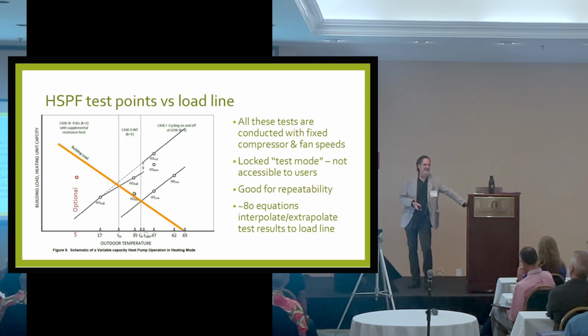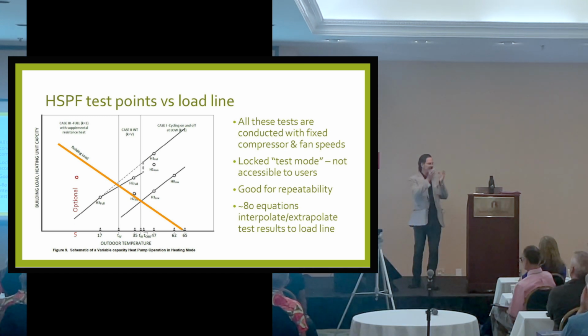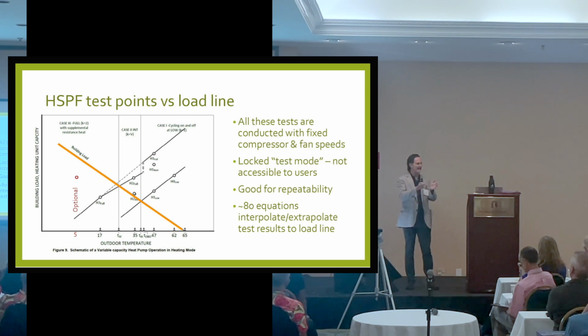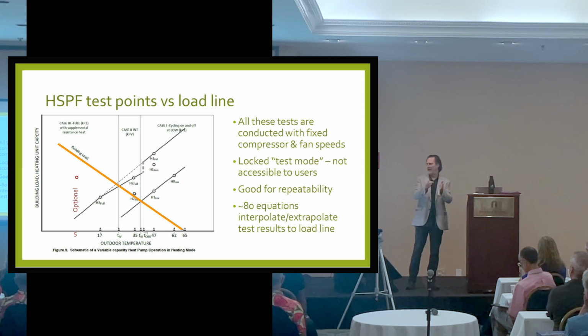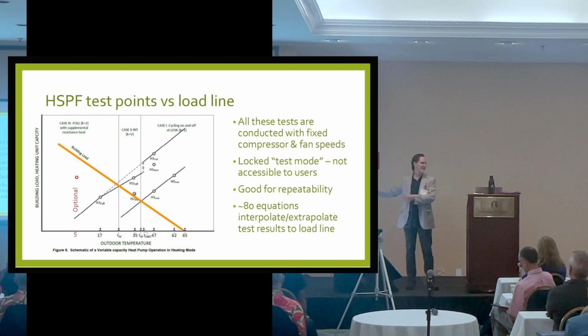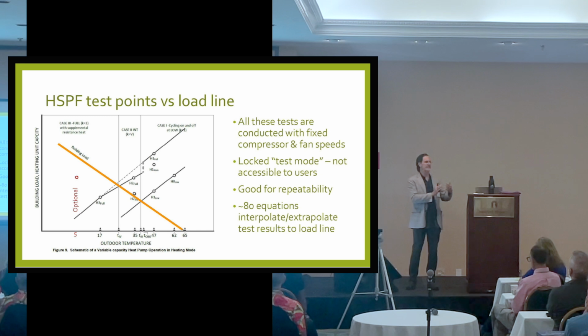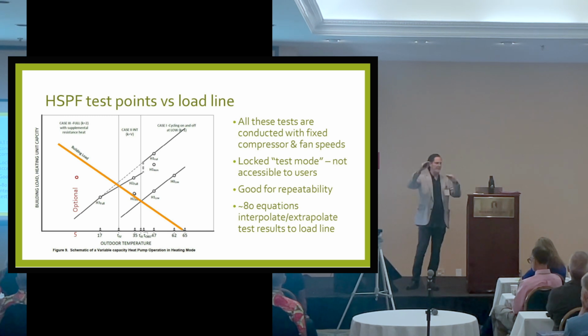All of these tests are conducted at fixed compressor speeds and fixed fan speeds. Some of those speeds are dictated specifically by the standard. Some have leeway within a certain boundary based on the measured cooling capacity of the equipment in the cooling mode. And some, the manufacturer can choose within a fairly wide range, but the different speeds have to relate to each other in a certain way.